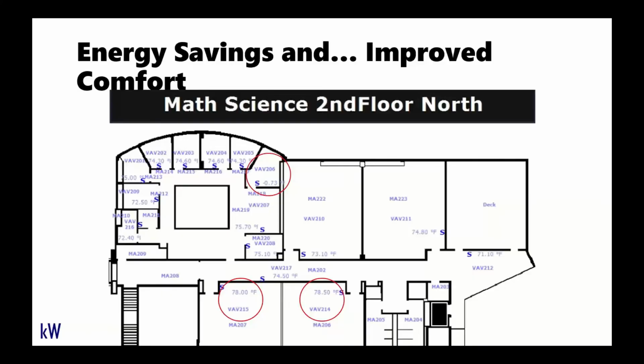So these can cause energy problems if this is causing excess heating, if the sensor is bad, or if a zone like this is driving cooling supply temperature resets. But it's also a comfort issue. Obviously, if these zone temperatures are accurate, which we verified they were, then the occupants in these areas are likely not going to be comfortable. And that results in excess hot and cold calls that go to the facility staff and bog down their otherwise already very busy workflow with additional nuisance requests.